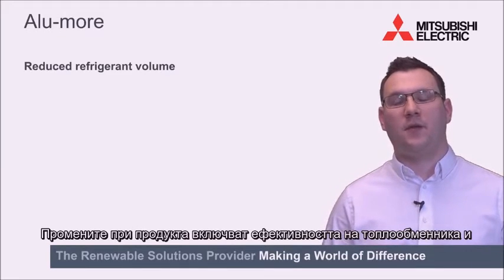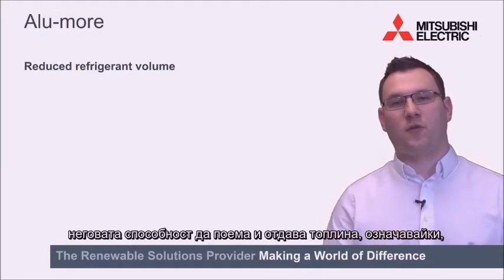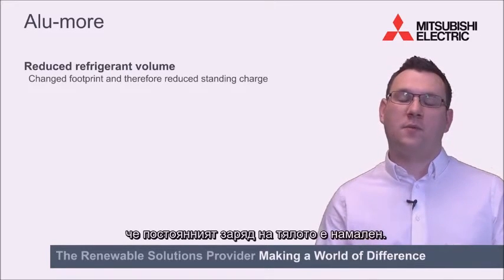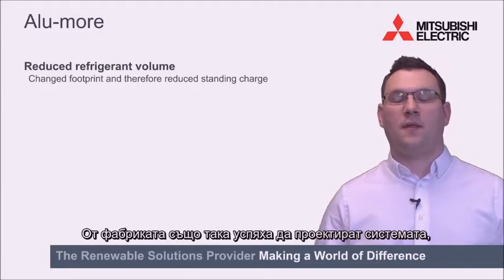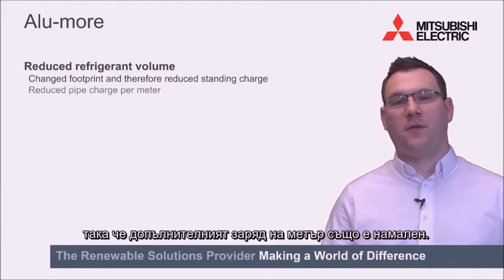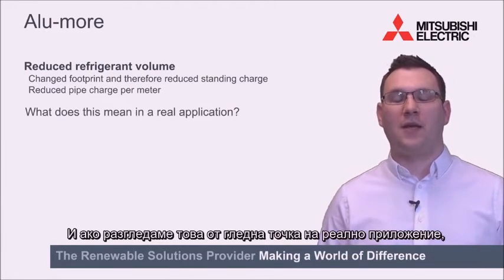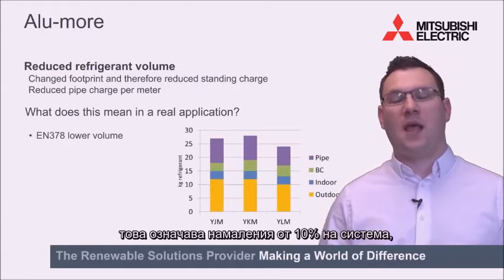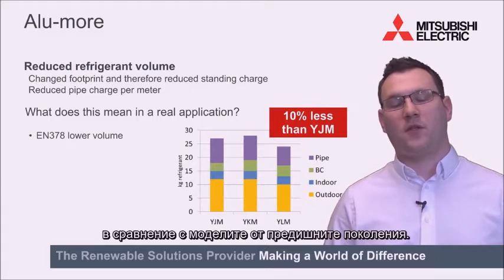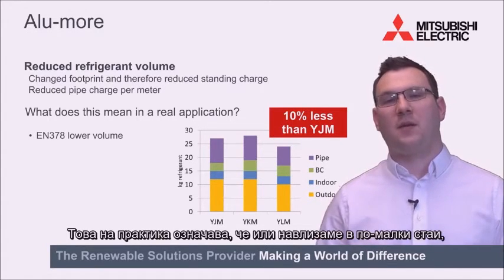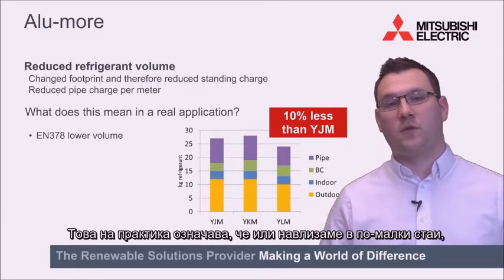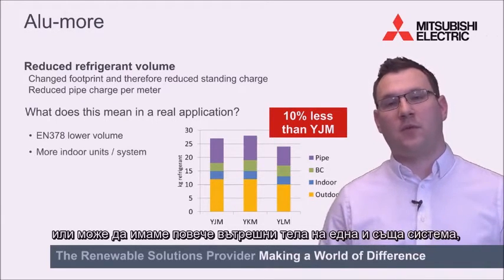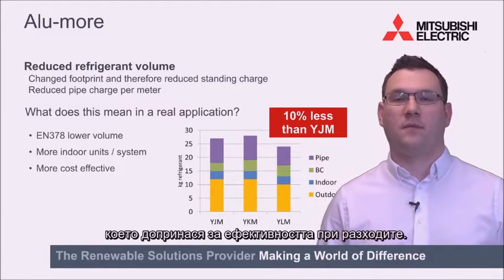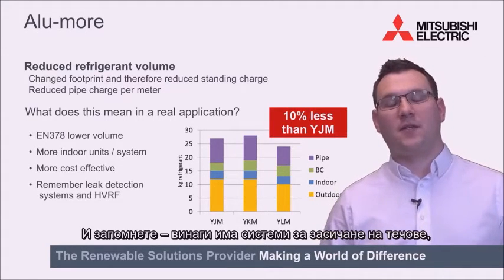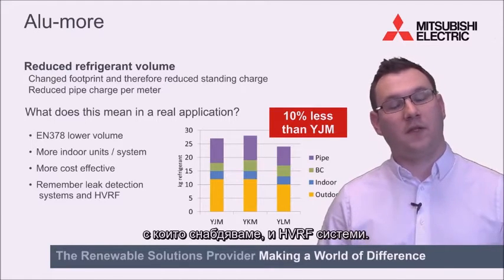The product changes include the efficiency of the heat exchanger and its ability to absorb and reject heat, meaning the standing charge that comes with the unit is reduced. The factory have also managed to design the system so the amount of additional charge per metre is also reduced. And if we look at this in terms of a real application, we're looking at reductions in terms of 10% on a system compared to the previous generation product. And what this essentially means is we can either go into smaller bedrooms or we can have more indoor units on the same system, making it much more cost effective. And remember, there's always those leak detection systems which we supply, or the HVRF system.